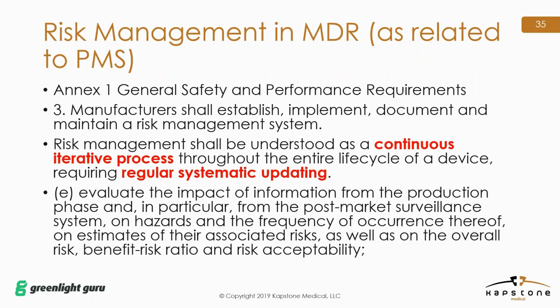Now just to touch a little bit on risk management in the EU MDR as related to post-market surveillance. In Annex 1, which describes your general safety and performance requirements, section 3 requires a risk management system that is continuous and iterative and requires systematic updating. So that's very important. It's continuous, like your post-market surveillance. It's the entire lifetime of the device, with regular systematic updating. So you need a procedure to drive that.